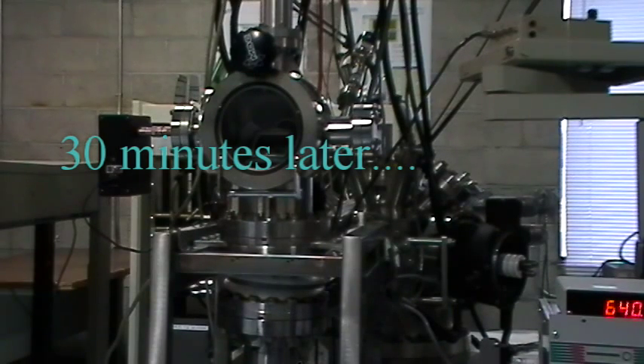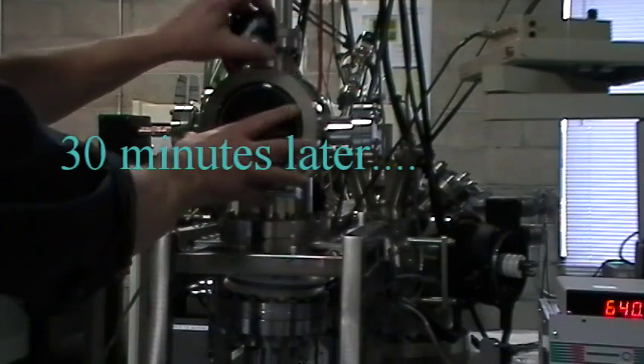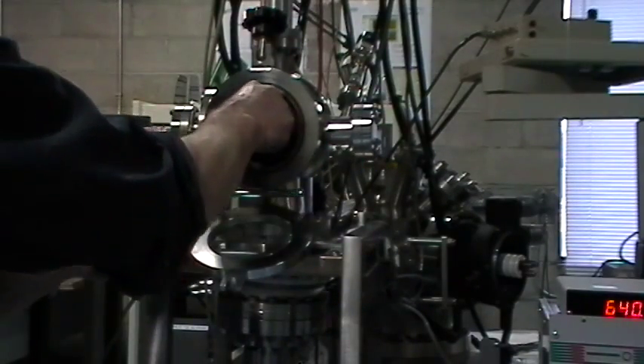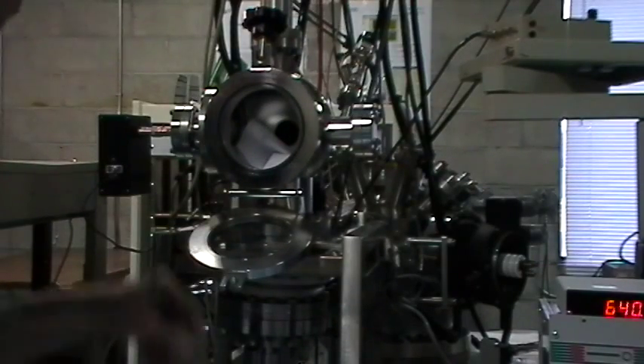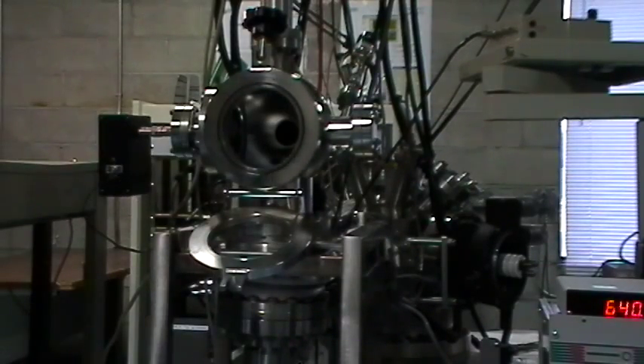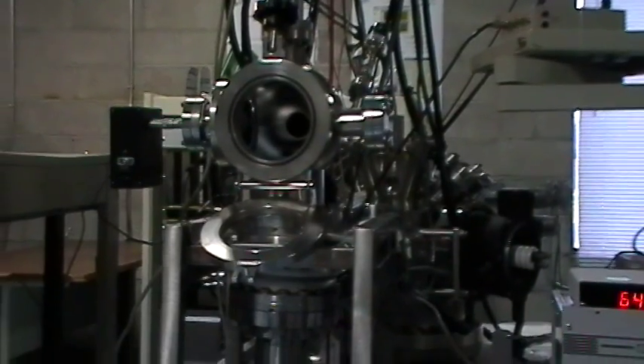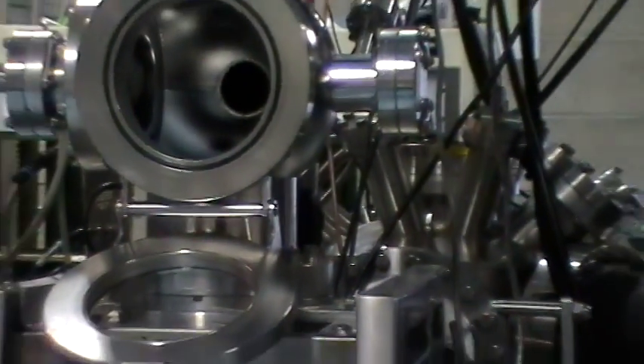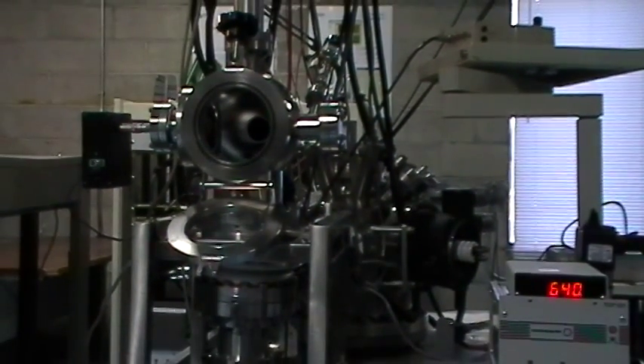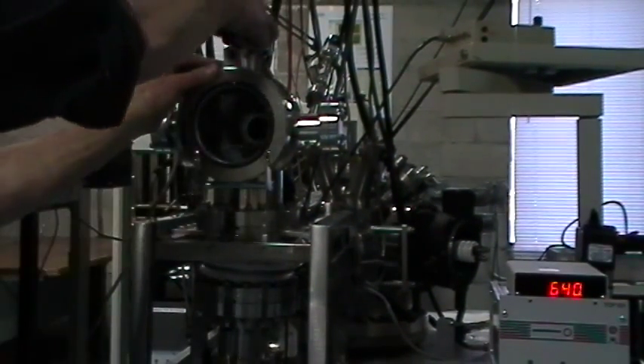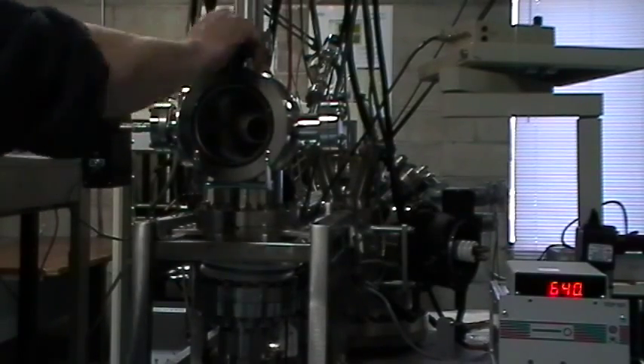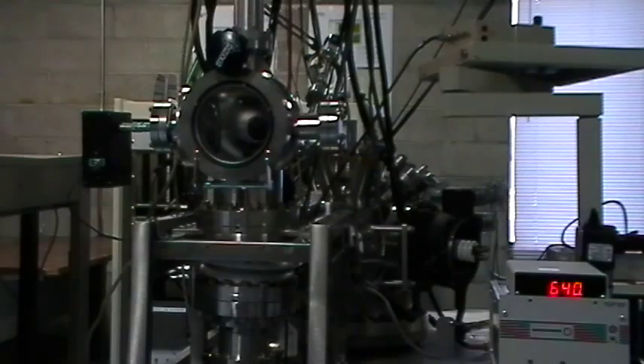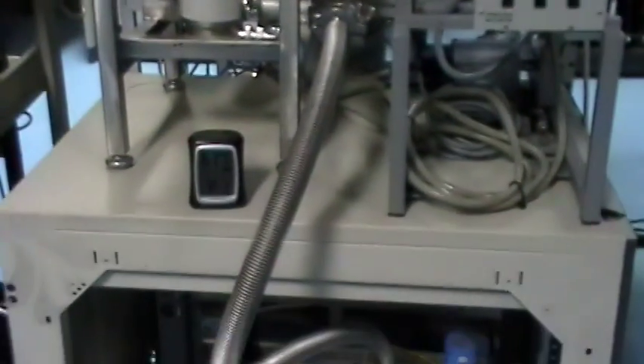Okay, 30 minutes later, we're going to remove the paper, and we had also inserted a humidity monitor so we could see what the humidity would be. It's increased up to about 63% from 27%. So we will close the load lock hatch, and we will start the pump down process.